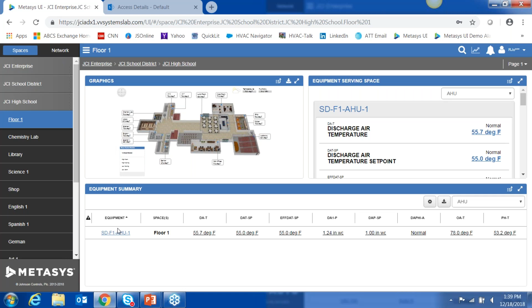So let's go to an air handler and pick a commandable point, like the discharge air temperature set point for the air handler feeding conditioned air to floor 1. I'm going to click on that point and try to command it. You'll see under the command dialog box there are several different options: an adjust, an override, some releases, and a change default value. You might be asking yourselves, as our operators often have, what's the difference between an adjust and an override? The difference is priority, basically.